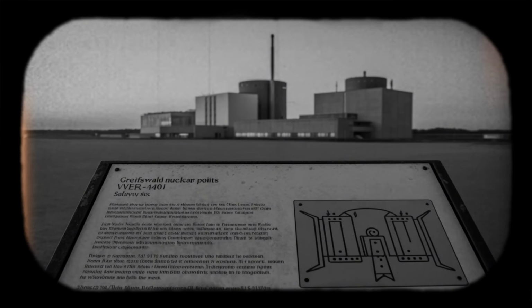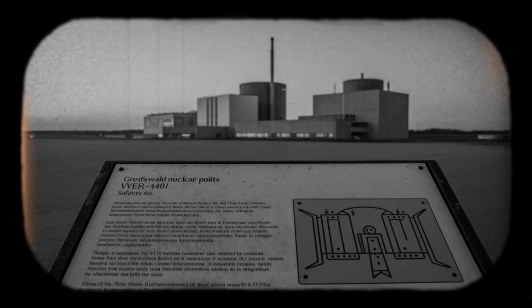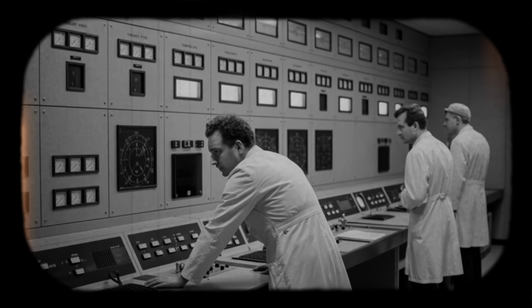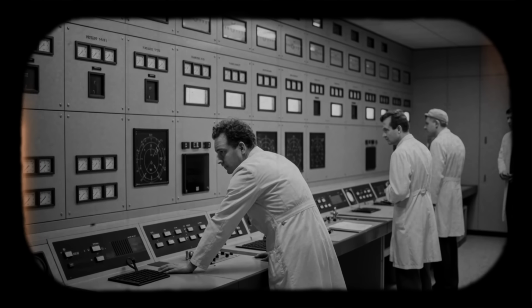But separation exists in design documents and in physical reality. And at Greifswald, reality differed from design in one critical aspect: common cable ducts with limited barriers between redundant trains. A single fault in the 6 kV system could propagate along shared routes, affecting several safety-related systems simultaneously. The Nuclear Energy Agency's post-event analysis would note this vulnerability explicitly.